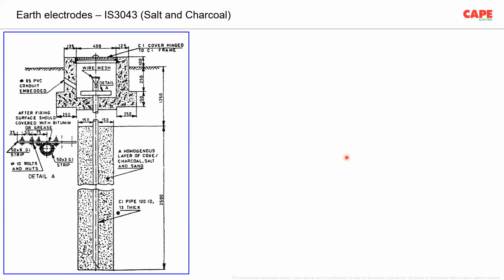But imagine in an installation, you forget to connect to the earth electrode. Still you are safe, because a person who is touching a live conductor accidentally may get a shock, but before the shock is hazardous, or before the shock is serious, the RCCB trips. In IS 3043, you can see two pictures.